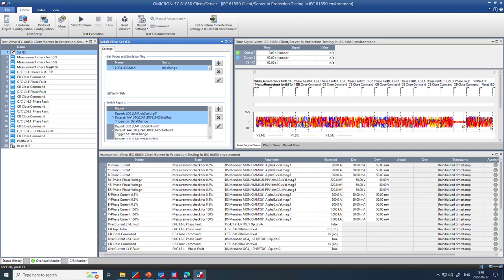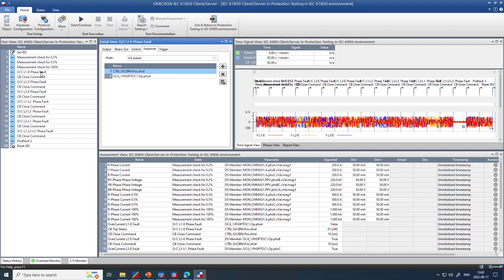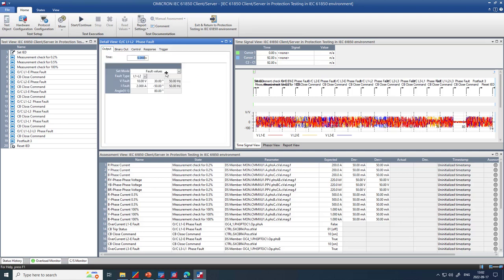So after verification of different percentages of the measurement signal, this is like a wiring check before we start the actual test of simulating the fault scenarios, so that we make sure that the sample values are properly published and the IED is monitoring the right values. And next, I'm going to use the different fault scenarios like phase overcurrent fault for different phases, and phase to phase fault and three phase fault.